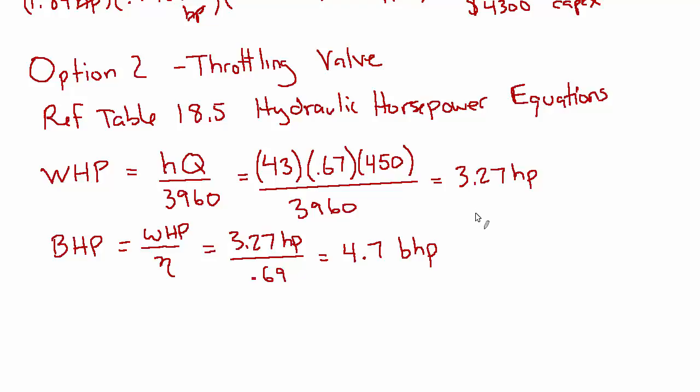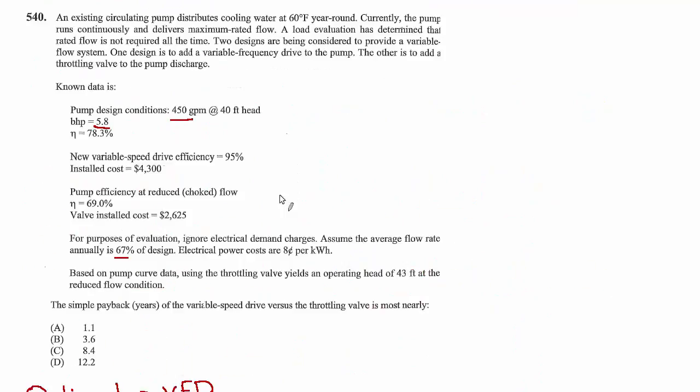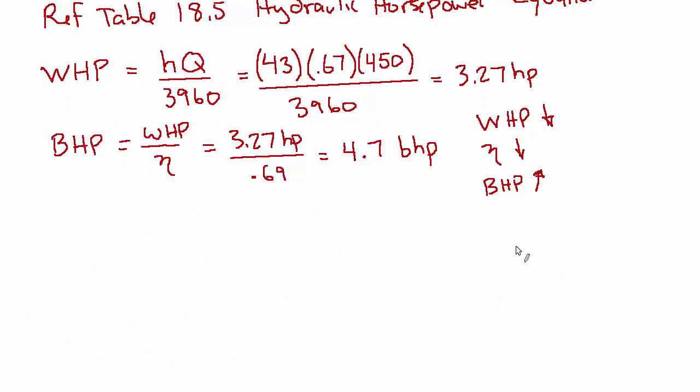So again, as we came from the original design, the water horsepower went down. If that wasn't the case, then we wouldn't do the project because there wouldn't be savings. But unfortunately, the efficiency also went down, which means that the brake horsepower went up from what it would have been. But it's still less than 5.8. And that's the key. It's still worth it. It's just a matter of which option is more worth it.